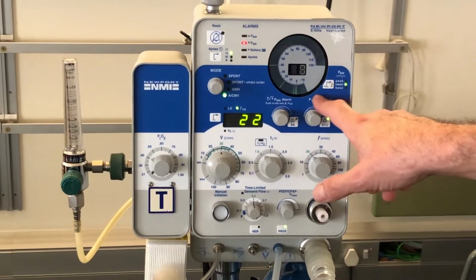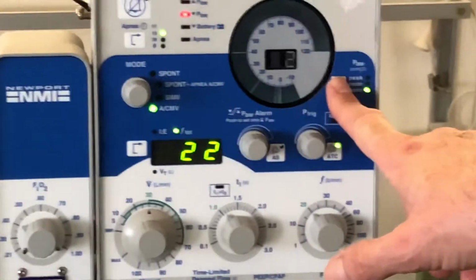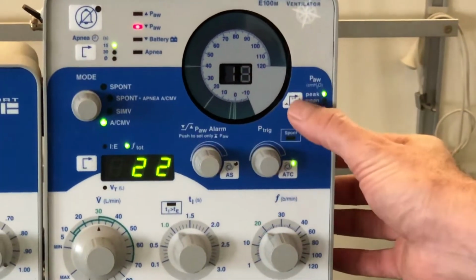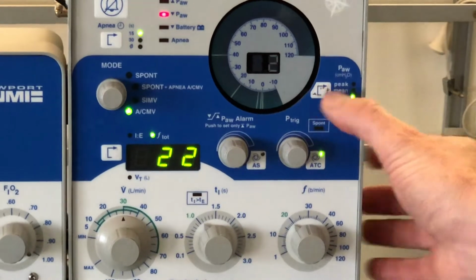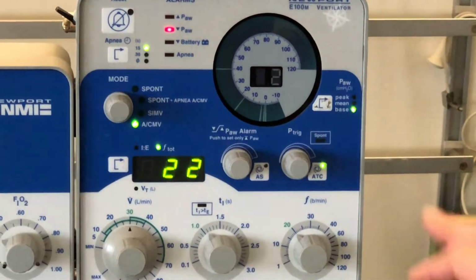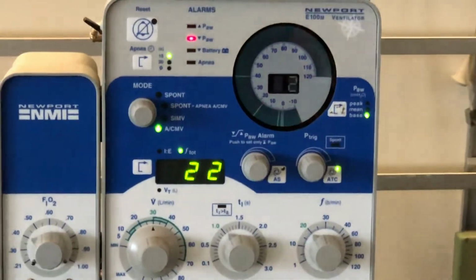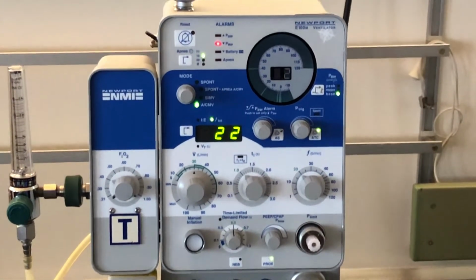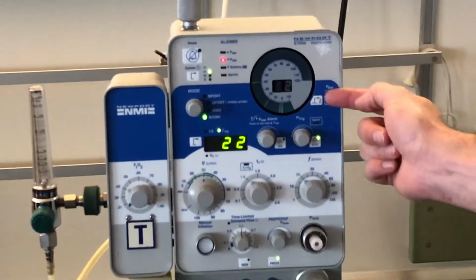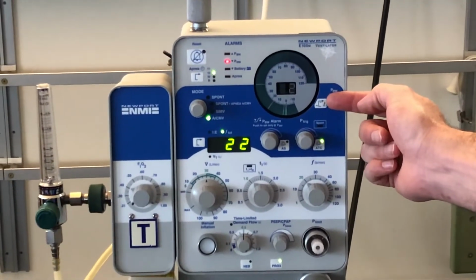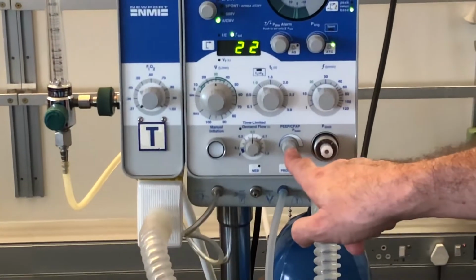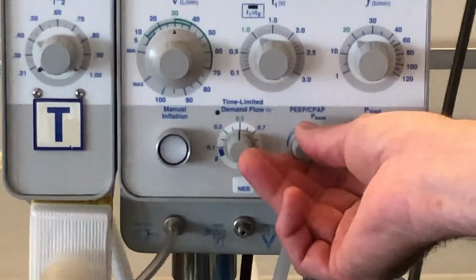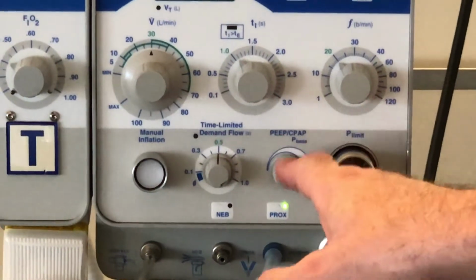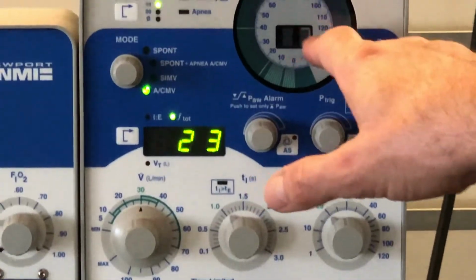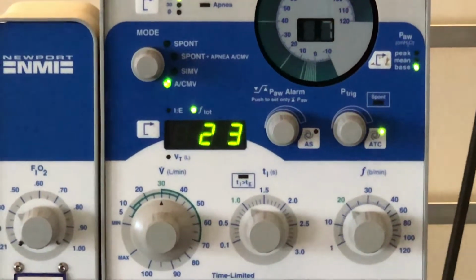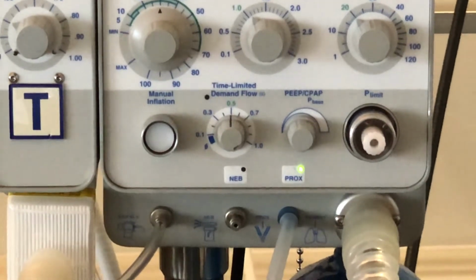All right, and then just above the trigger setting over here, we've got a selector which we can use to get the machine to display the peak airway pressure, the mean airway pressure, and the base pressure for the machine. The base pressure is just another way of saying the PEEP that's been set on the machine. Because we've got to the PEEP monitoring here, I'm going to skip ahead to setting PEEP. And to set PEEP, we use the third dial in the bottom row, and we wind that slowly to increase the PEEP level. And while we change the setting here, we watch constantly what the machine is reading the baseline pressure as in that central display.